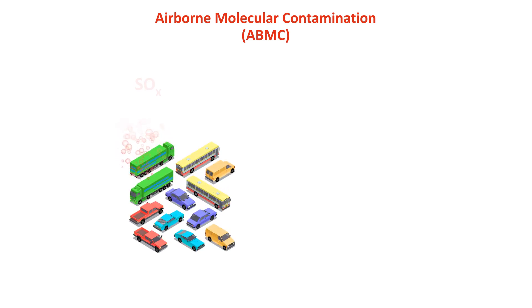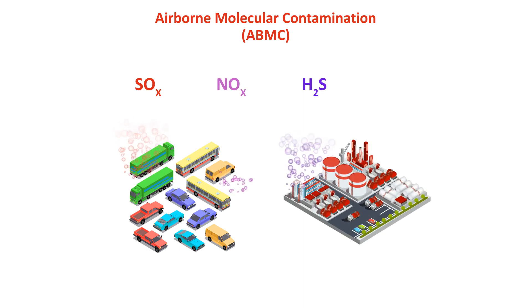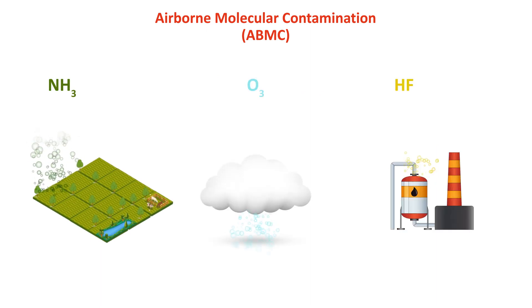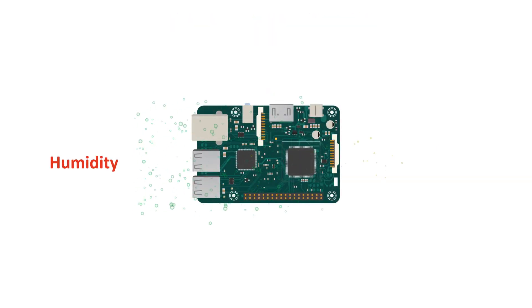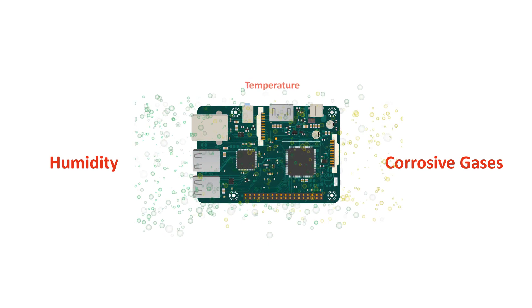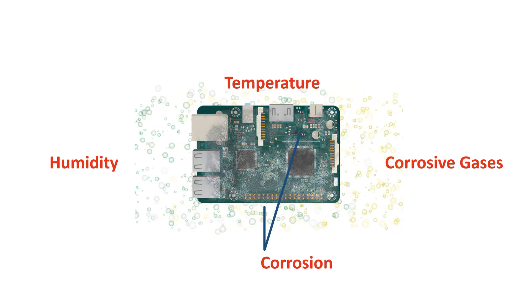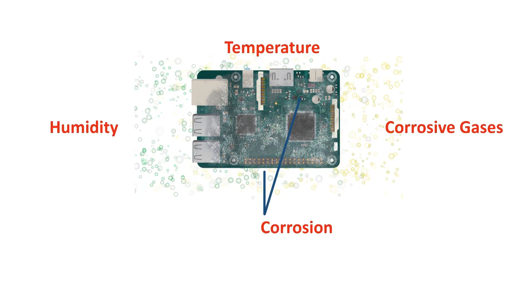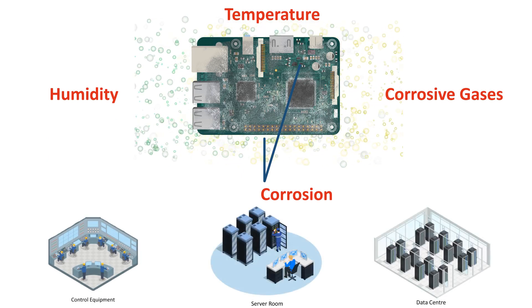Airborne molecular contamination, or AMC, is mainly due to the vapors of contaminant gases like compounds of sulfur, SOx, H2S, oxides of nitrogen, NOx, chlorine compounds, ammonia, NH3, O3, HF and volatile organic compounds, VOCs. High relative humidity in combination with corrosive gases corrodes electronic circuits and other control equipment, and hence adversely affects the operation, reliability and longevity of sensitive automated process control equipment, server rooms and data centers of various industries.